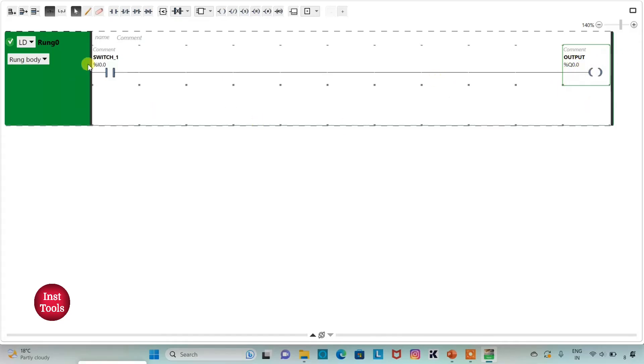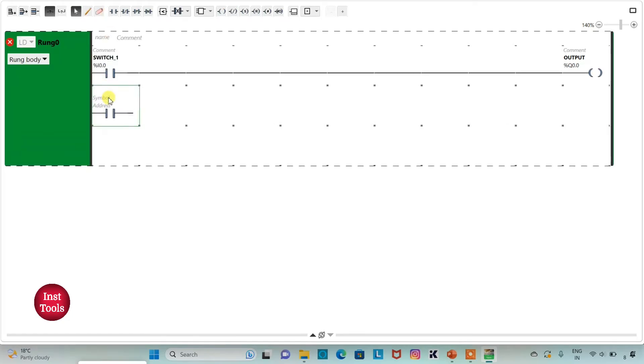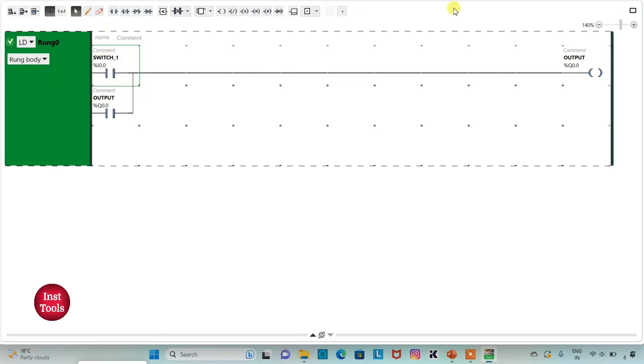But when switch1 is turned off, the output should remain on. So in this case, we will latch it. I will insert one more normally open contact and assign address Q0.0 to it, which is the output, then draw a line to connect it. So when switch1 is turned on, output will be on, and when switch1 is turned off, output will remain on because we have latched it here.